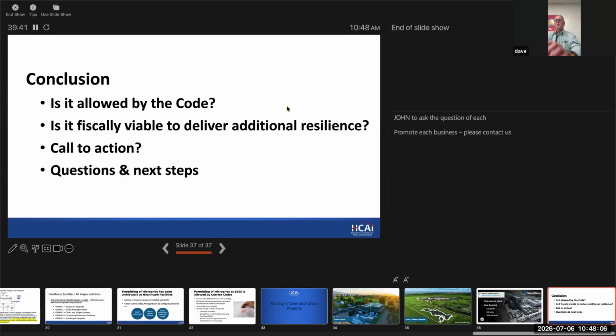And so what happens is they have a full complement of emergency generators, and they have this connected to the normal system. So in the event of a power outage, it's a seamless transition, and the occupants don't know that they've lost utility because the fuel cell, the microgrid, assumes all the load. And what we saw during commissioning is that the generators start, but they never pick up the load. They're there, available, and the signal is sent as soon as utility is lost. But because of the seamless transition to the fuel cell, to the microgrid, it assumes all of the load, and the transfer switches never transfer to the emergency generators, and it carries.